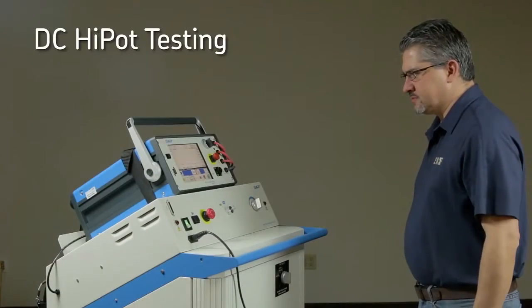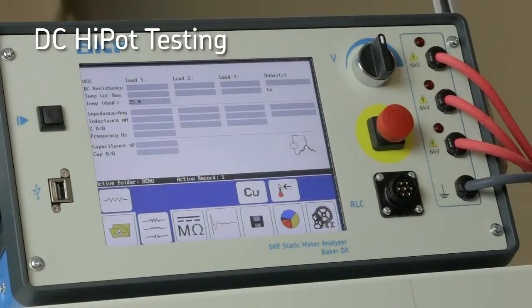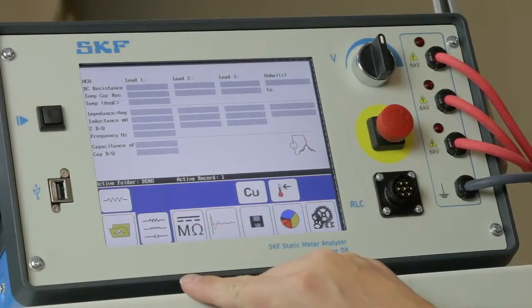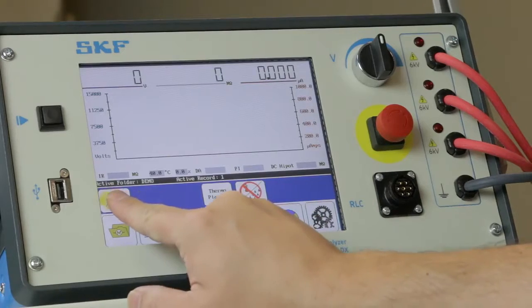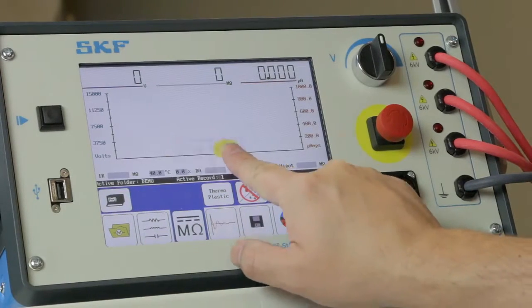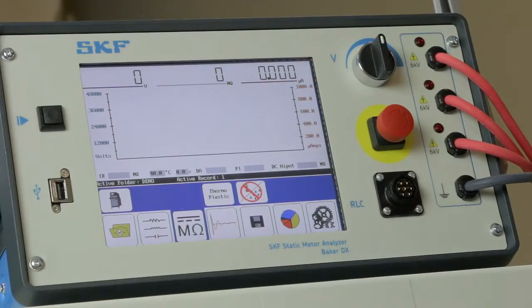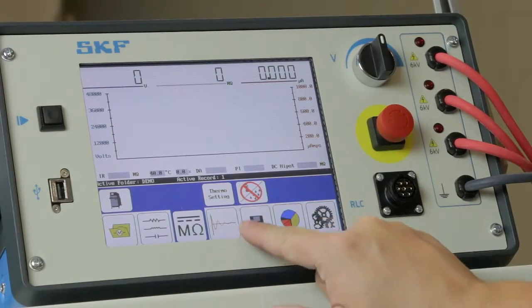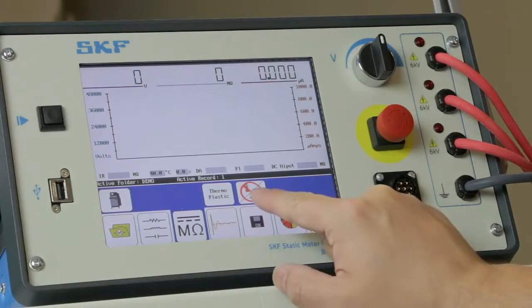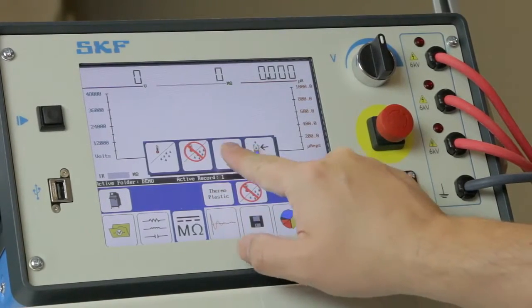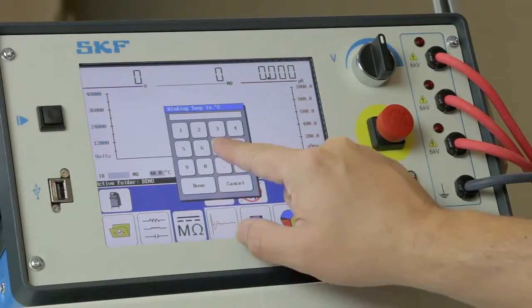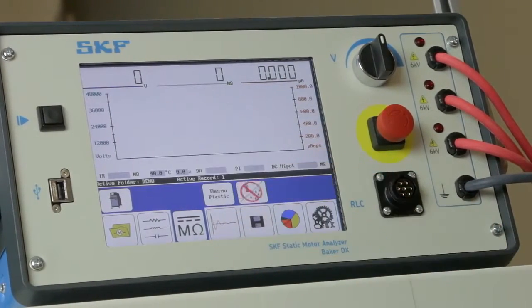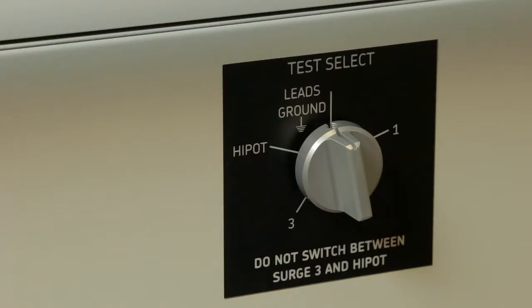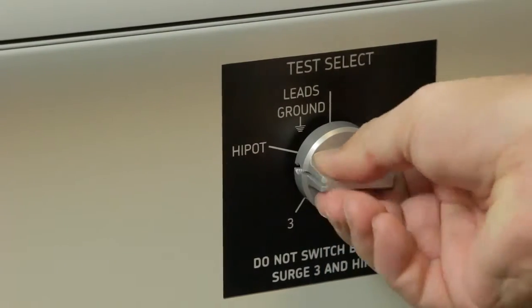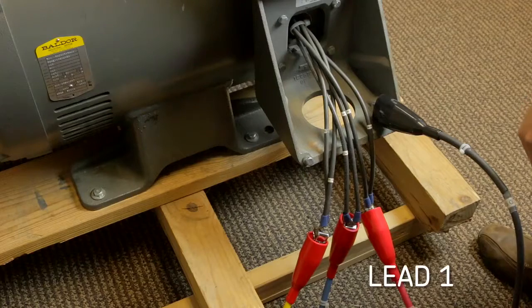Let's start with DC HiPot testing. On the main screen of the DX, select the DC test. Select the power pack configuration. Select either thermoplastic or thermoset, corresponding to the type of insulation being tested. Enter the stator winding temperature. Turn the test selector switch to the HiPot position. It is important to note that only lead 1 will be energized during the HiPot test.